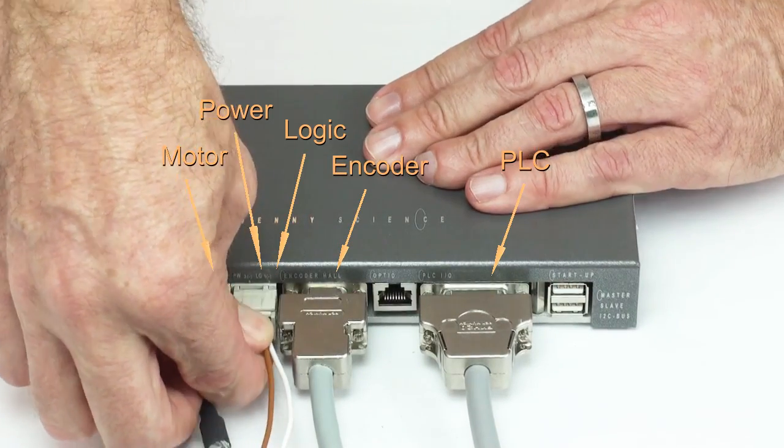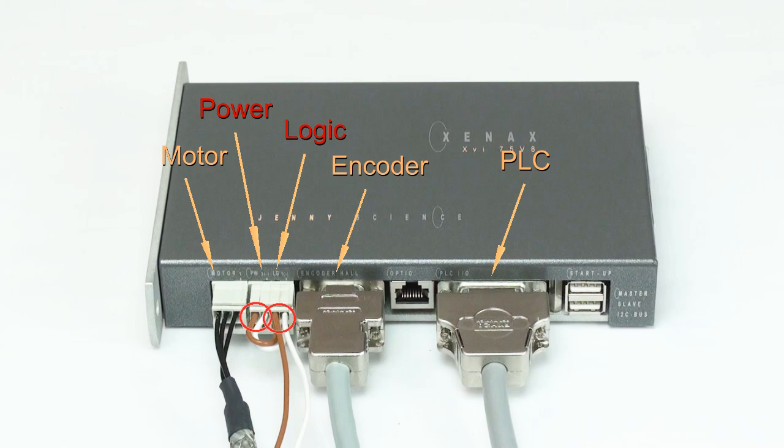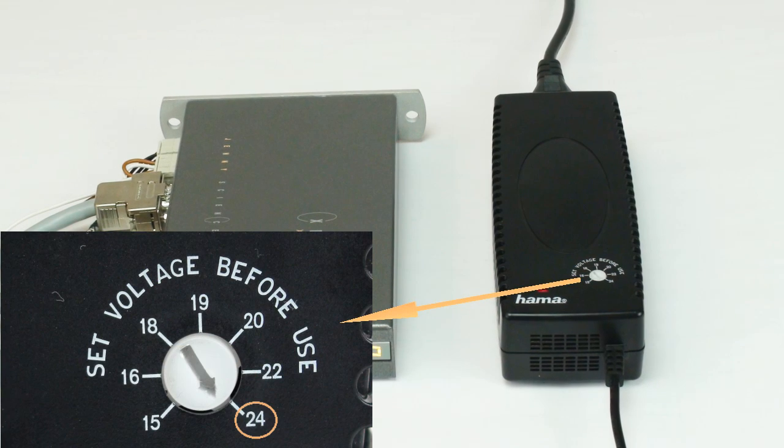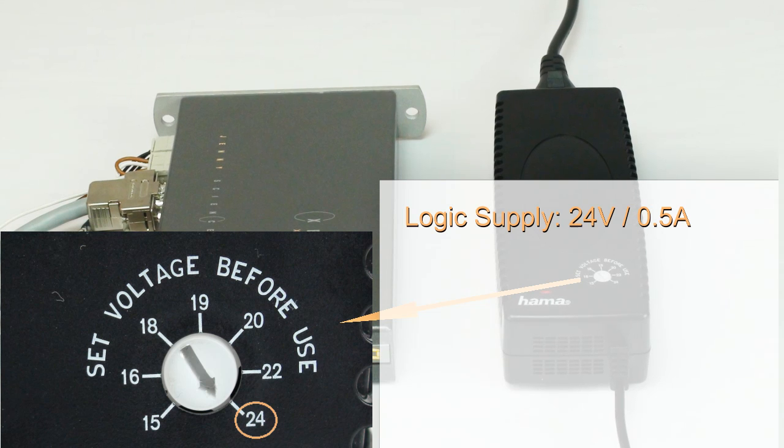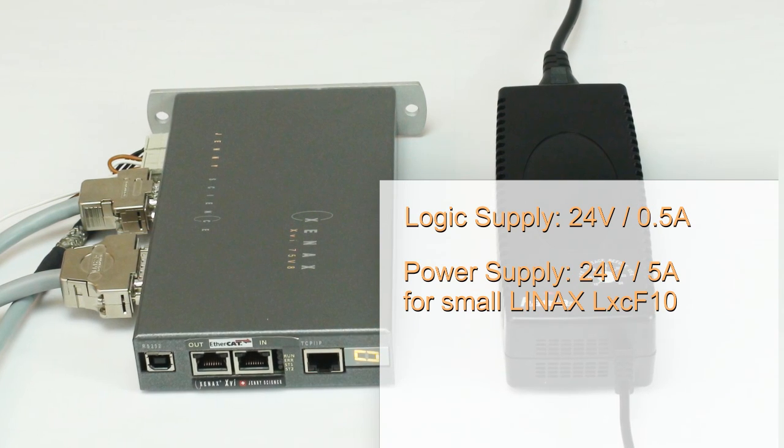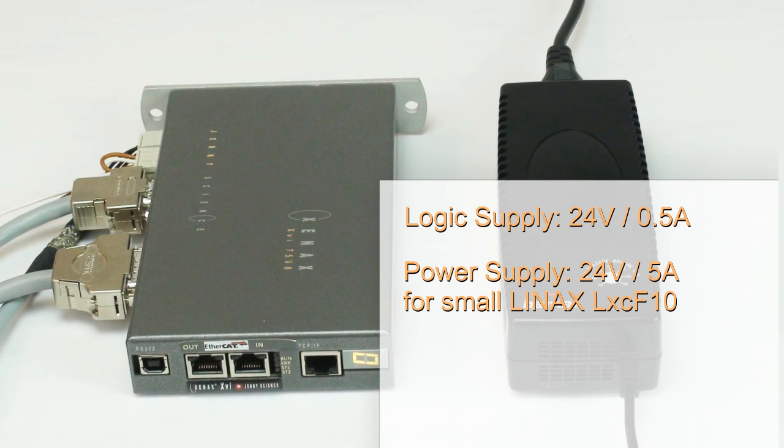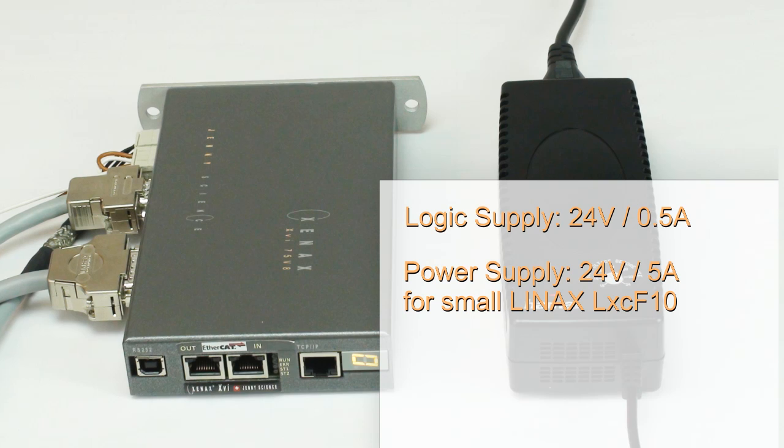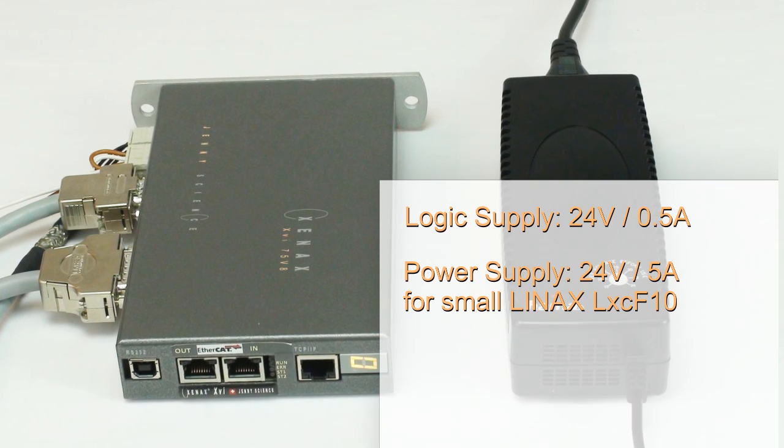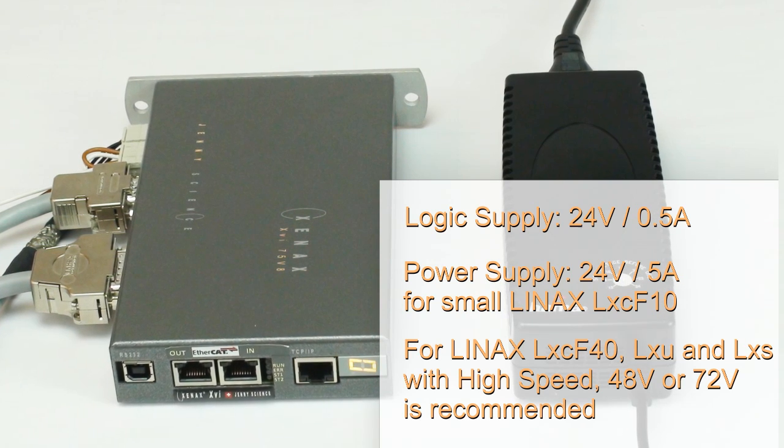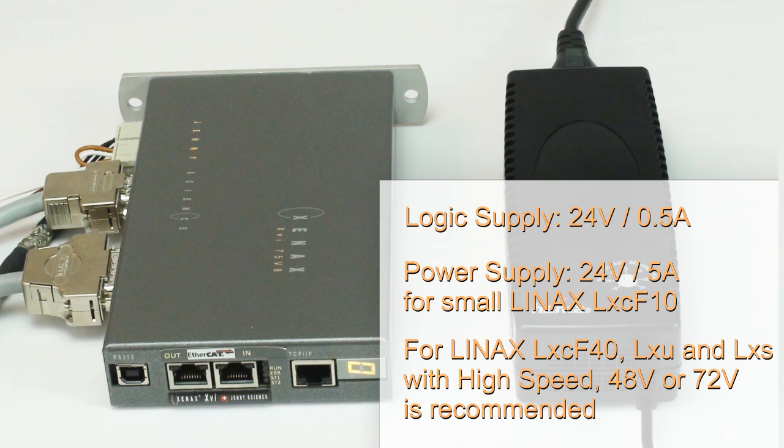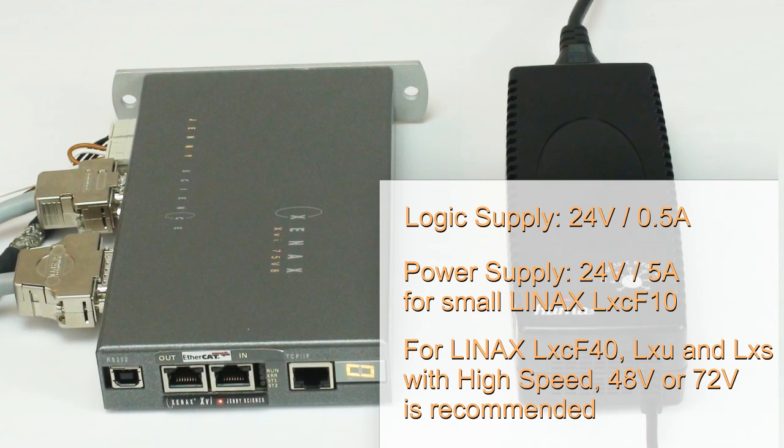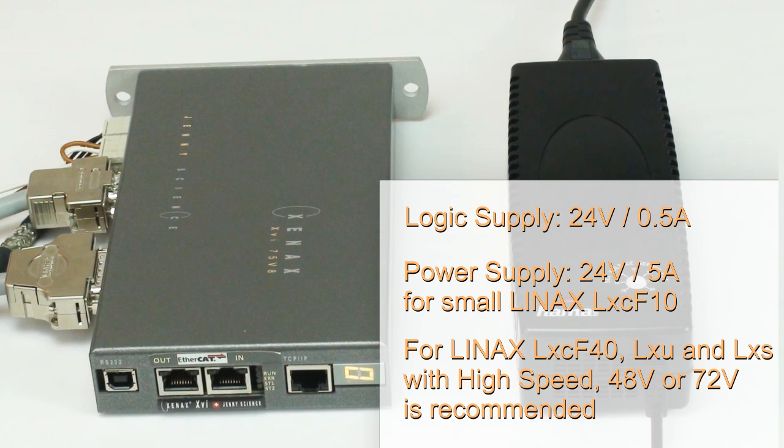Xenax has TCP IP and real-time Ethernet technology. The logic supply is always 24V DC. The logic consumes about 500mA. The power supply ranges from 24V to 72V DC. For larger axis and for higher speed, a 48V or 72V DC power supply is recommended.